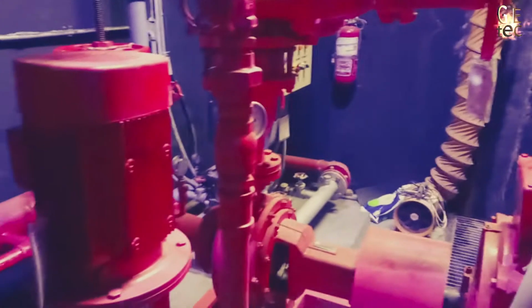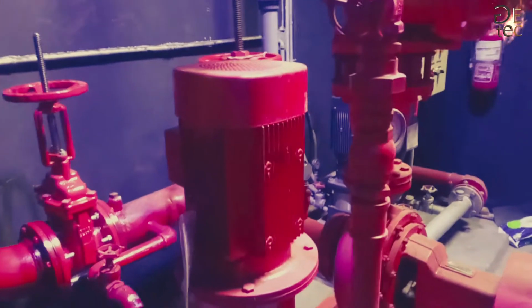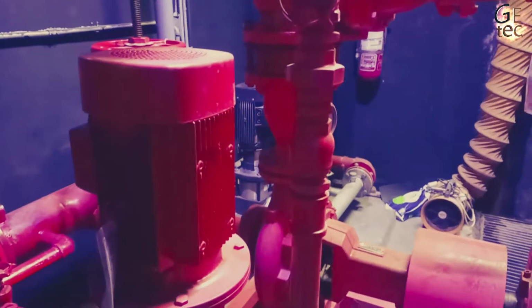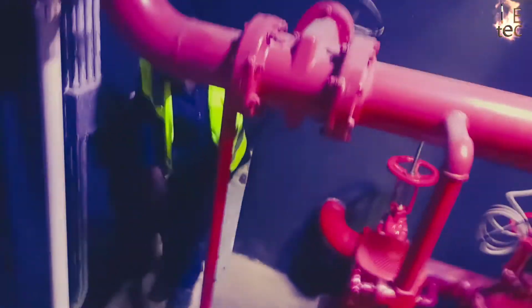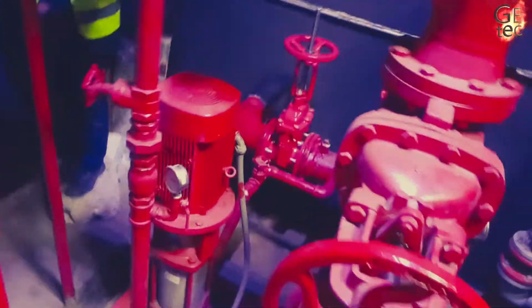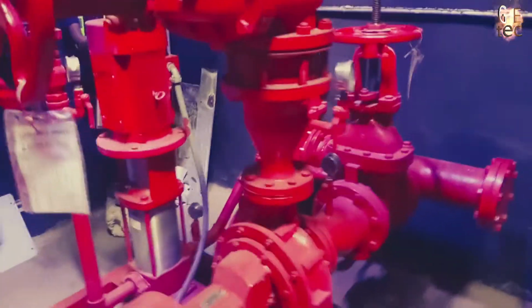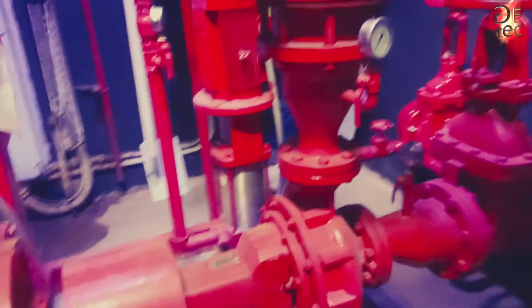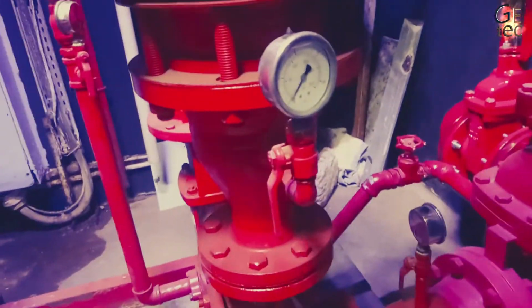The purpose of the jockey pump is to keep the water pressure in the pipes within a specific range when there's not a fire, so that the sprinklers won't go off randomly. Since pipes leak, over time, the water pressure inside them automatically goes down. The jockey pump senses this, and then fills them back up to normal pressure. If a fire happens and the pressure drops dramatically, the jockey pump won't be able to keep up, and the drop in pressure will trigger the large fire pump to start sending water.